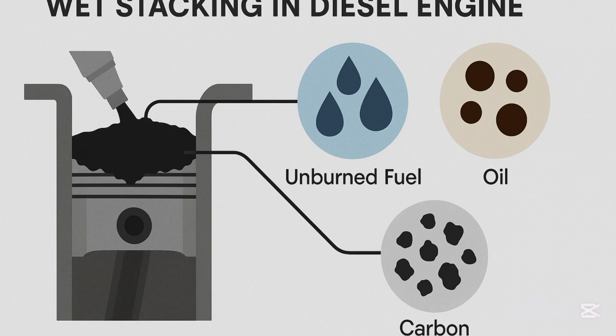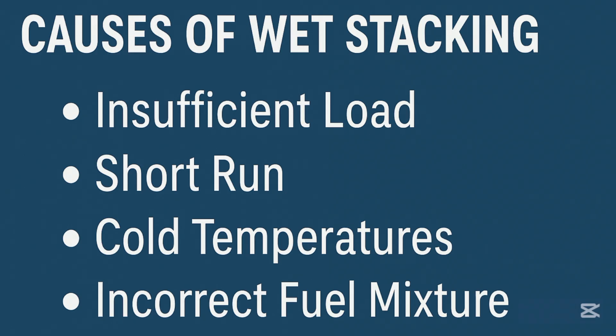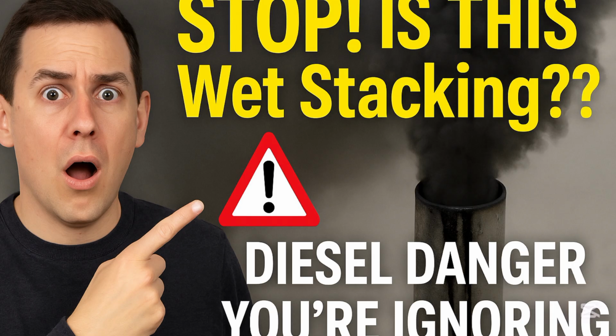Number two is short trips. When you run short trips too frequently, or with a generator, when you run it for only 10 to 15 minutes, you are going to have wet stacking.